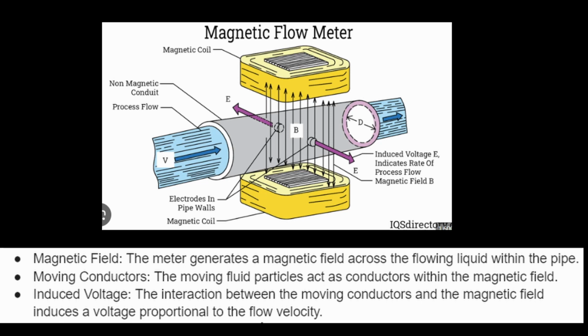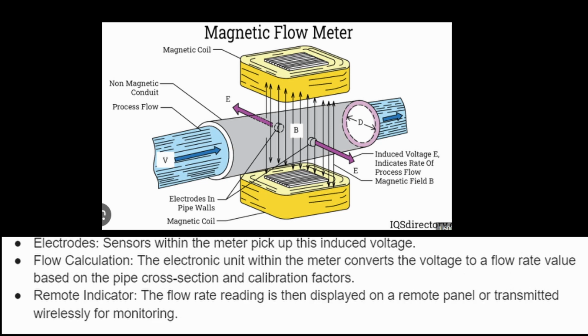Magnetic field. The meter generates a magnetic field across the flowing liquid within the pipe. Moving conductors. The moving fluid particles act as conductors within the magnetic field. Induced voltage. The interaction between the moving conductors and the magnetic field induces a voltage proportional to the flow velocity. Electrodes. Sensors within the meter pick up this induced voltage. Flow calculation. The electronic unit within the meter converts the voltage to a flow rate value based on the pipe cross-section and calibration factors. Remote indicator. The flow rate reading is then displayed on a remote panel or transmitted wirelessly for monitoring.